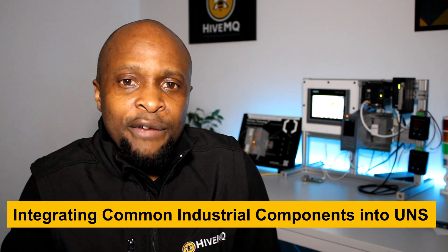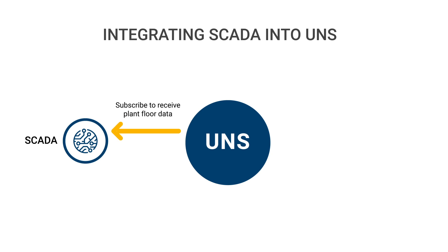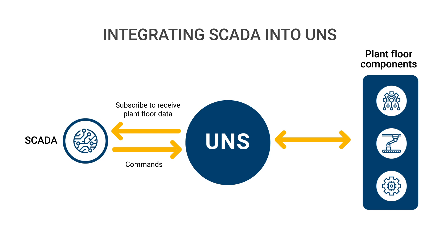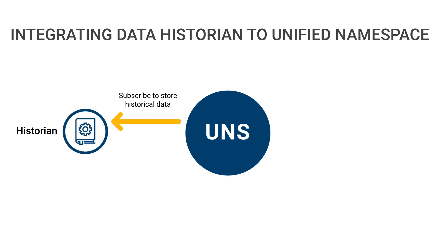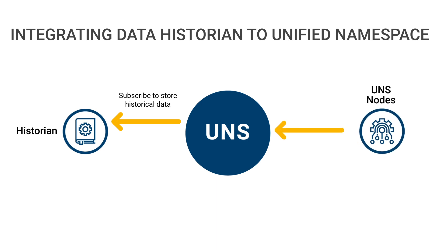Here is a look at how integrating data from common industrial components into a UNS could look. A SCADA system would subscribe to the unified namespace to receive all required data to allow plant operators to run production efficiently, and would also publish back to the UNS commands to be executed by nodes on the plant floor. Since the UNS doesn't capture historical data, a process historian would subscribe to topics of interest and store historical data for later retrieval. An MES also needs data from the plant floor to calculate business performance metrics such as OEE, or overall equipment effectiveness.